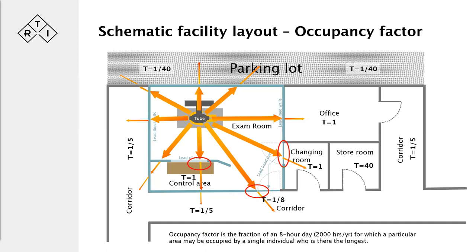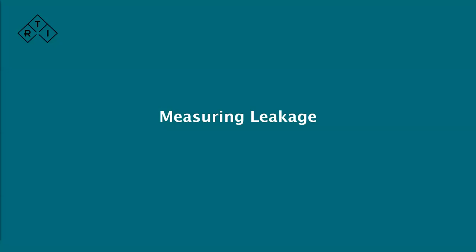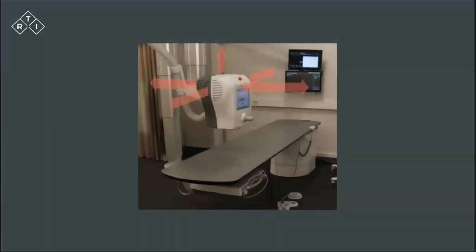Now let's discuss measuring leakage and scatter, starting with leakage. Since there is angular dependence on this type of radiation, leakage radiation is typically measured in five directions: front, rear, top, anode side, and cathode side. The distance from the focal spot to where you measure should be one meter. An instrument is needed to do this measurement.